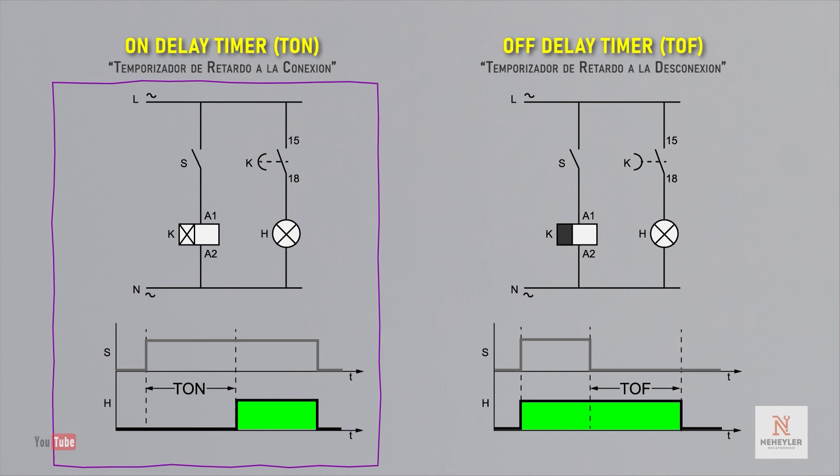If we open contact S to de-energize the coil, contact K of the timer immediately changes state and disconnects the circuit, since it only acts at the time of connection but not at disconnection.